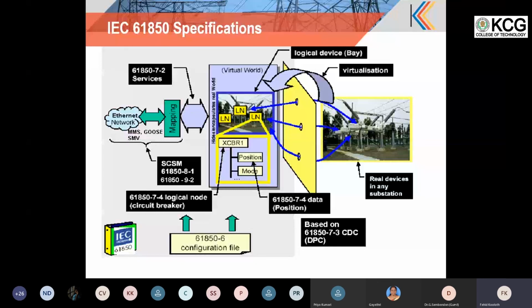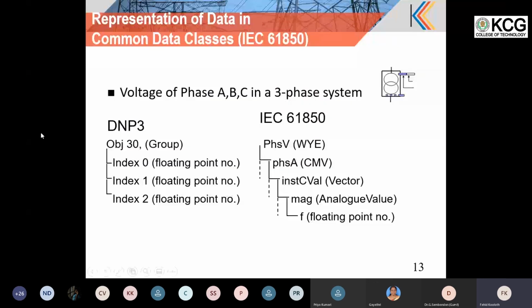So moving on to data representation, focusing on the data representation. As I mentioned, DNP3 is a standard. It goes object, index, and index can be for current, it can be 0, next time it can be 10, another device it can be 200, like that. But in 61850, it is specifically mentioned: phase voltage, phase A, instantaneous value, magnitude, and floating point. So it will come as PhV.phsA.instCVal.mag.f and .ang.f. Like that, every data is received in a structured, object-oriented manner in 61850. This allows 61850 devices to be auto-discovered from a client system.